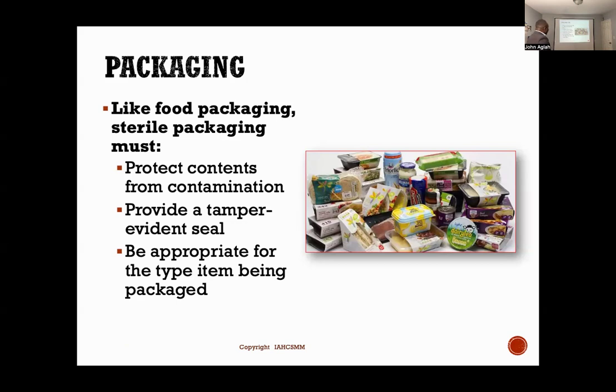Now, so apart from the tamper evidence, like the seal that is on milk and other regular packagings, the packaging must also be appropriate for the type and item being packaged, okay? The type and item being packaged. All right, so you can't just pick anything for any instrumentation. Doesn't work like that, right? Some of the packages are validated to go in steam. Some are validated to go in low temperature sterilization. You can't pick a container or a package that is validated to go in a steam sterilizer to go in a low temperature sterilizer. It doesn't work like that, okay?